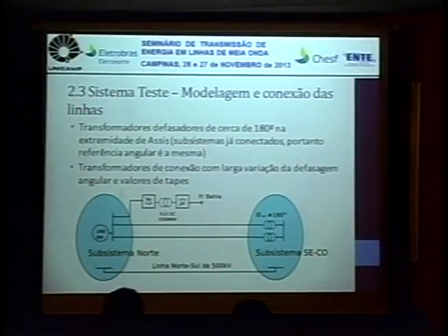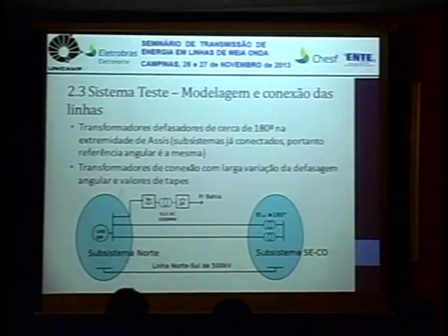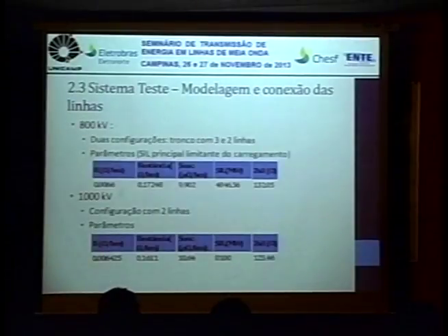Something that we introduced in this paper was that we can have some gains in these performance levels by adjusting. So besides these 180-degree transformers, we could adjust this slightly to improve these performance levels. This was something that was also worked on in this project. These are data from the lines, both from 800 kV and 1000 kV. This characteristic power for each one: 4100 is the characteristic power for the 1000 kV line, and 2800 the characteristic power for the 800 kV line.